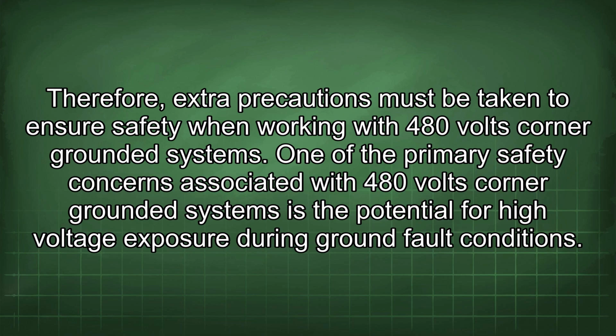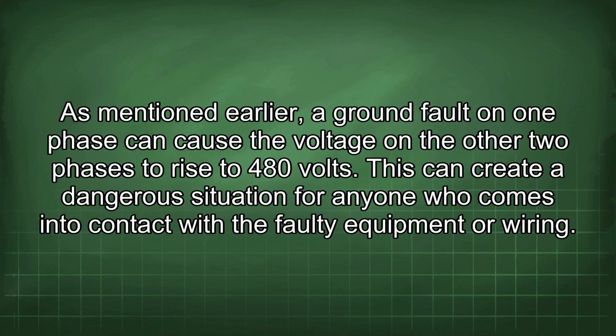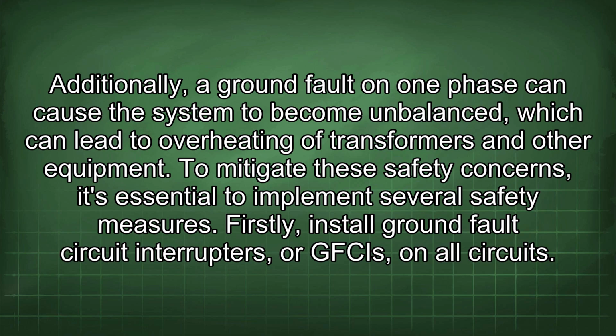One of the primary safety concerns associated with 480 volts corner-grounded systems is the potential for high voltage exposure during ground fault conditions. As mentioned earlier, a ground fault on one phase can cause the voltage on the other two phases to rise to 480 volts. This can create a dangerous situation for anyone who comes into contact with the faulty equipment or wiring. Additionally, a ground fault on one phase can cause the system to become unbalanced, which can lead to overheating of transformers and other equipment. To mitigate these safety concerns, it's essential to implement several safety measures.